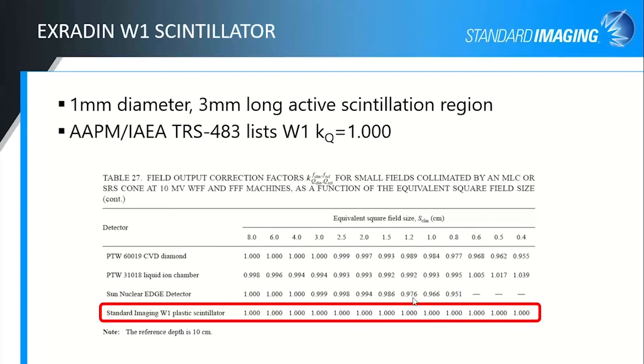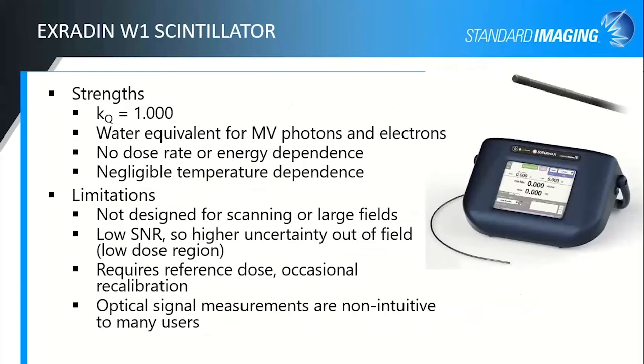You'll notice some other detectors, as you get down below 5 centimeters, you start to need corrections with a lot of those chambers or other detectors. And where the publication does not list values, it's because the uncertainty was too high and they didn't recommend that detector be used for those field sizes at all. So that's always a fun table to point out to people. I always enjoy that one.